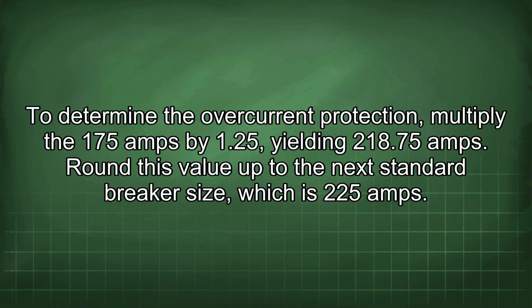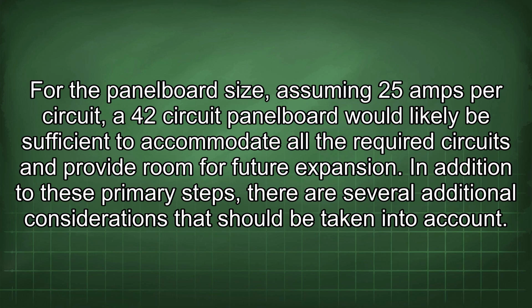To determine the overcurrent protection, multiply the 175 amps by 1.25, yielding 218.75 amps. Round this value up to the next standard breaker size, which is 225 amps. For the panel board size, assuming 25 amps per circuit, a 42-circuit panel board would likely be sufficient to accommodate all the required circuits and provide room for future expansion.